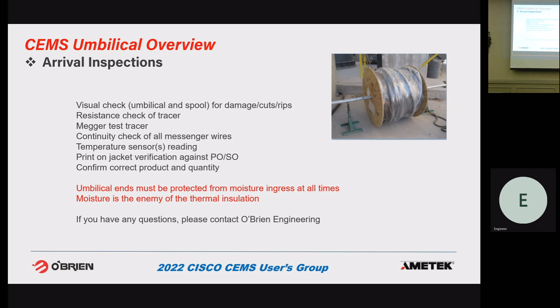Also, if there's a cut in the jacket and you're not installing it for a couple of weeks, it sits out in the field and water gets in there. I've got this on a bunch of slides - the number one reason for pre-insulated tubing bundle failure is moisture getting in. Moisture gets into the thermal insulation, which reduces its insulating quality, so you get more heat loss. At a minimum, you won't be able to maintain temperature in that area. It could even make the tracer overheat, maybe fail, maybe overheat the tubes. So any cuts, we want to address right then.